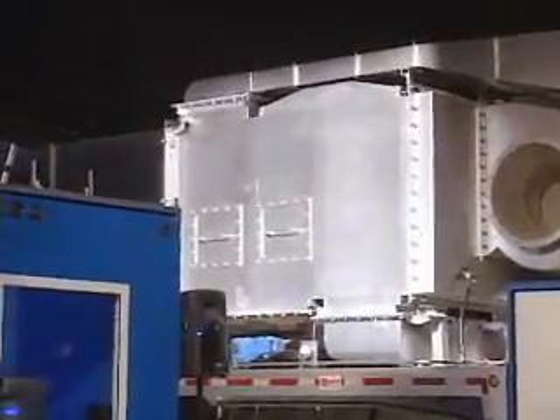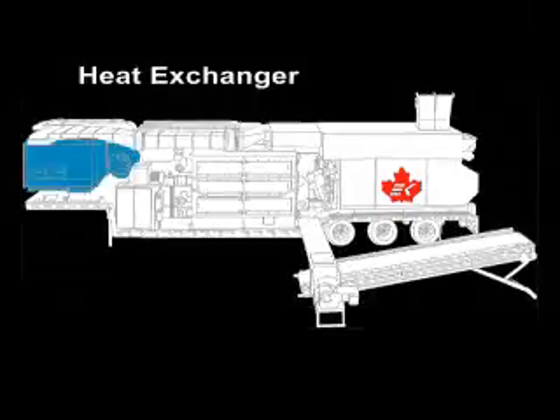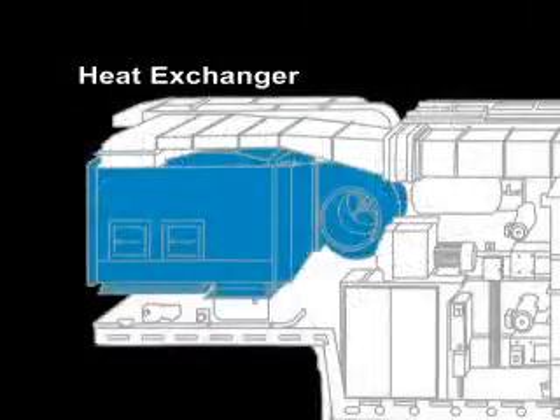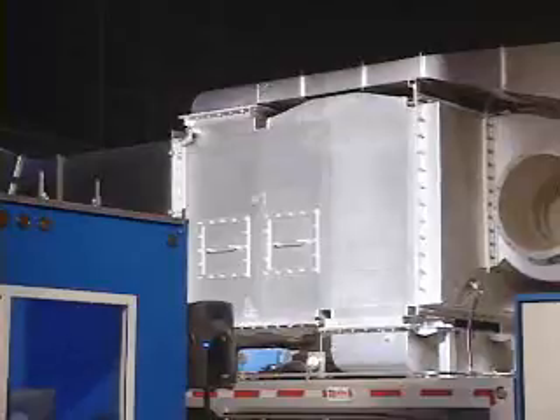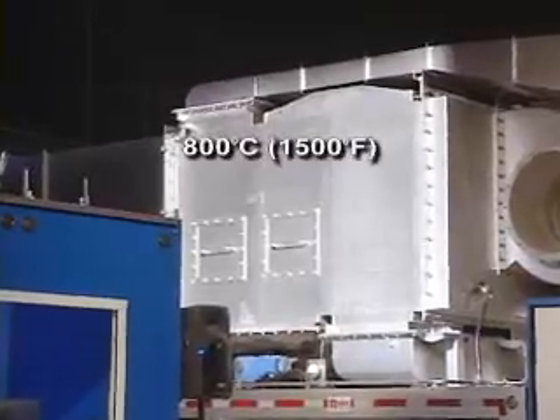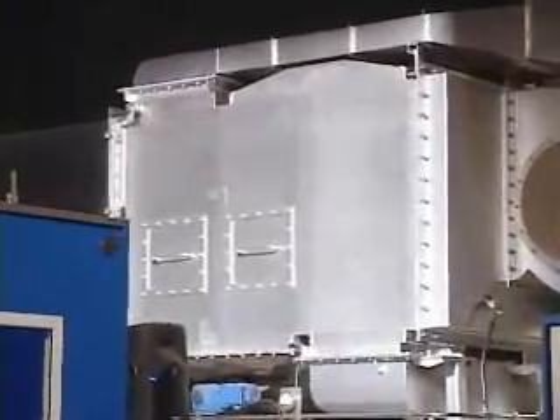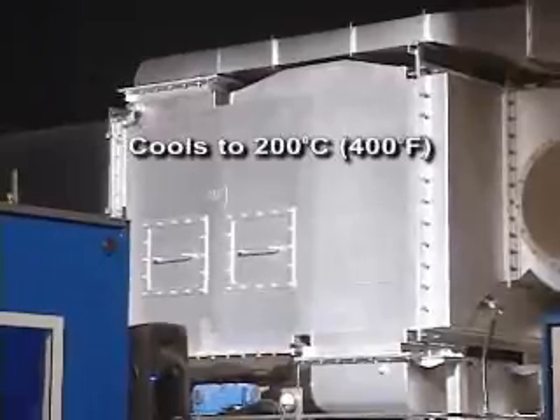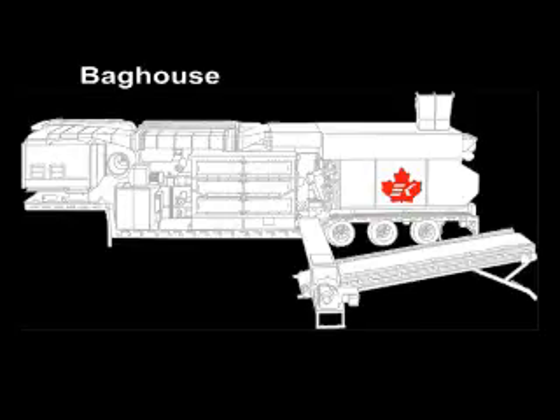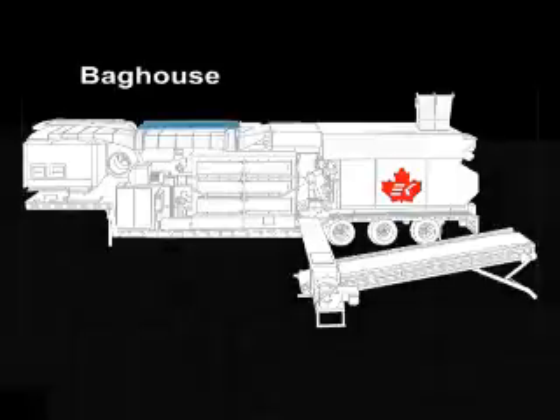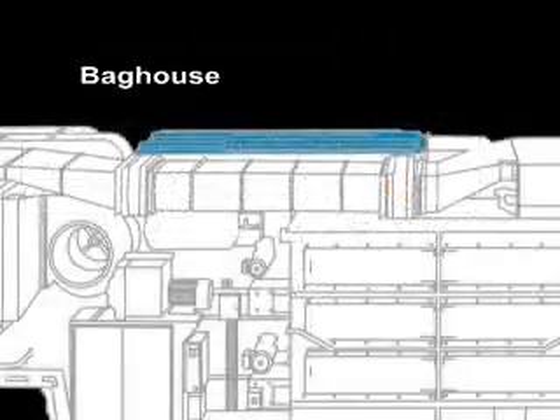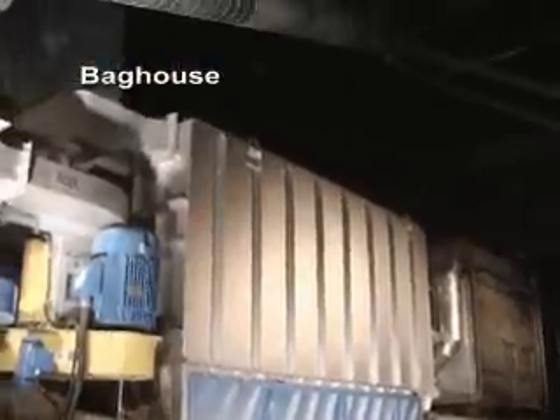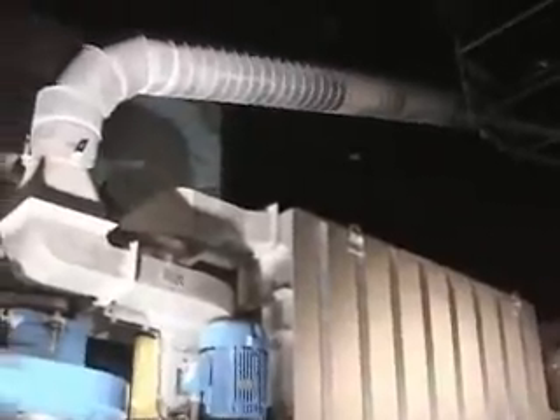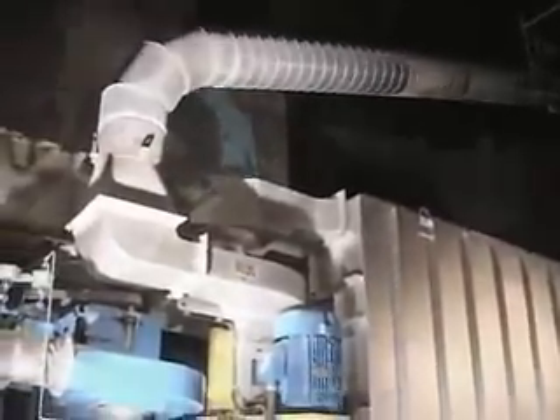The heat exchanger sits on the front of the machine, and since the oxidizer typically runs at 800 C, it cools the air rapidly to a temperature appropriate for the baghouse, which is about 200 C. The baghouse is on the back of the machine and filters the now hydrocarbon-free particulate from the airstream. Since the air is now cleaned of hydrocarbons and particulate, it is ready to re-enter the atmosphere.